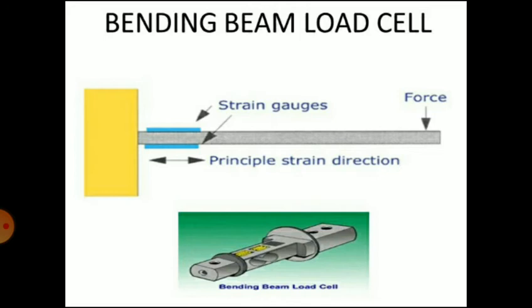Another type of load cell is the deflection or cantilever type load cell, or the bending beam load cell. You can see there is a cantilever beam, and on the top as well as at the bottom of the beam strain gauges are attached. When force is applied, there is a change in resistance that can be measured with the help of a Wheatstone bridge circuit.